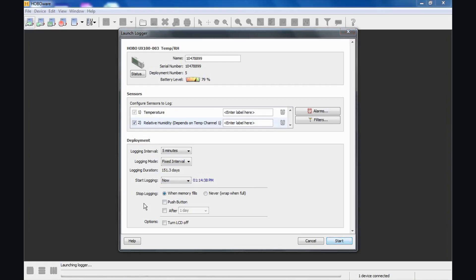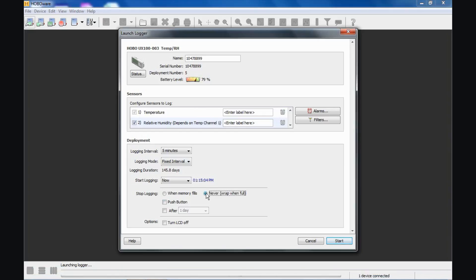There are several options for how you want the logger to stop its logging activities. By default, when you have a brand new logger, the logger will stop when the memory fills. So in this case with a five minute logging interval, it will stop logging at the end of the logging duration, 151.3 days. If we select never, this will allow the logger to overwrite old data with new data from the beginning of its memory when the memory fills. We call that wrapping. Some people call it circular logging. Some people call it first in, first out.